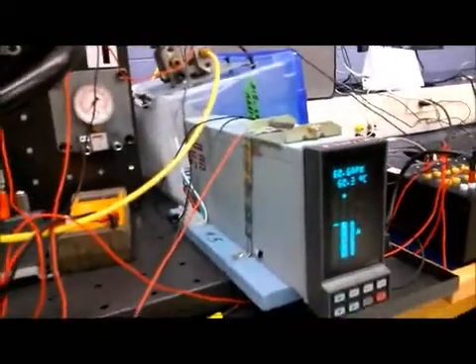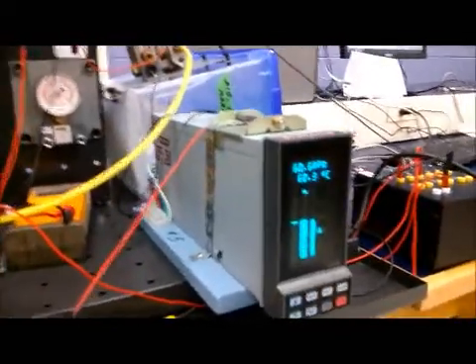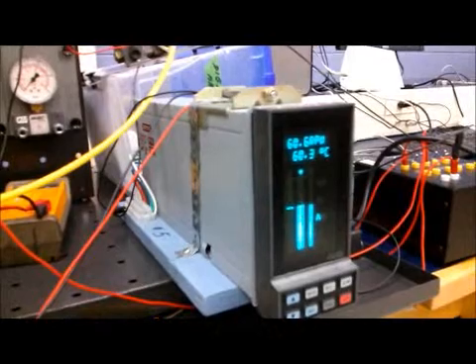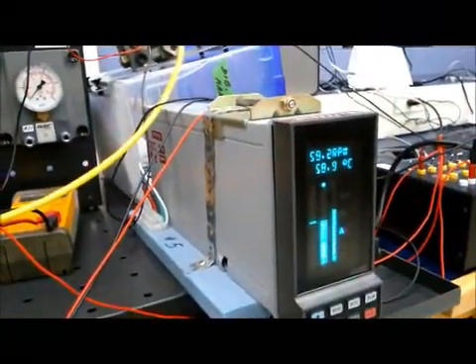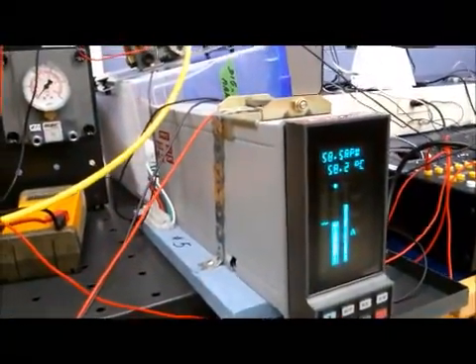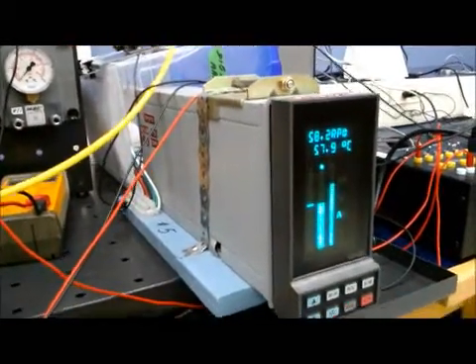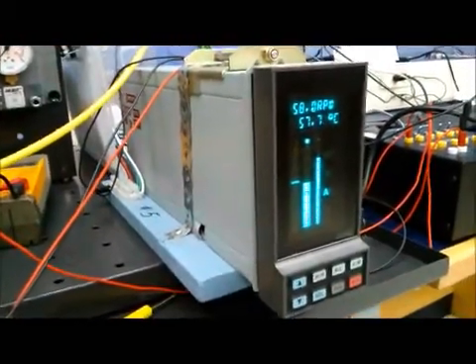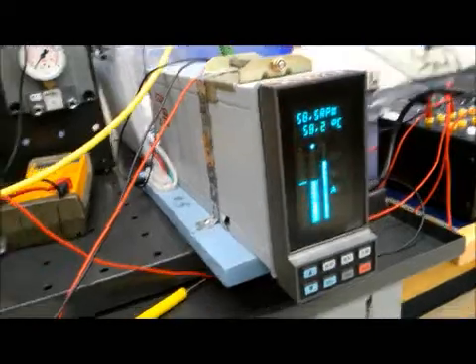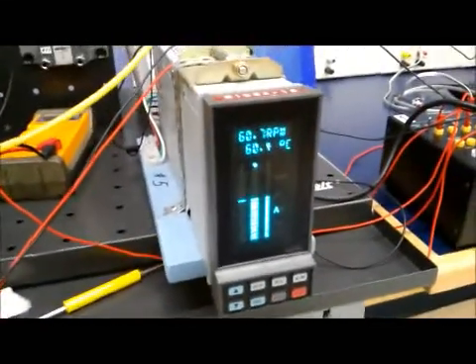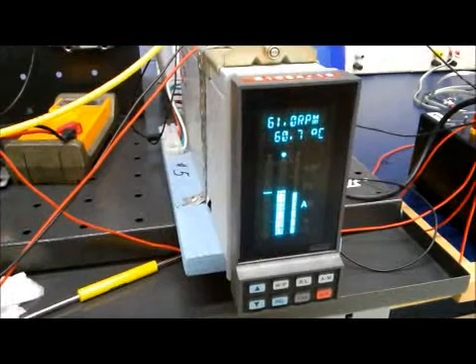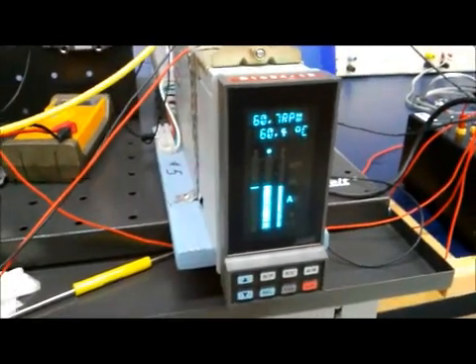As I open HV2 and cause, instead of pumping water into the system, it just pumps it back into the tank. You can see, the center one stays pretty well. And it increases the output to compensate. It's working quite well. At single loop level only. Output of the Foxboro controller is controlling the pump. We've got cascaded control.